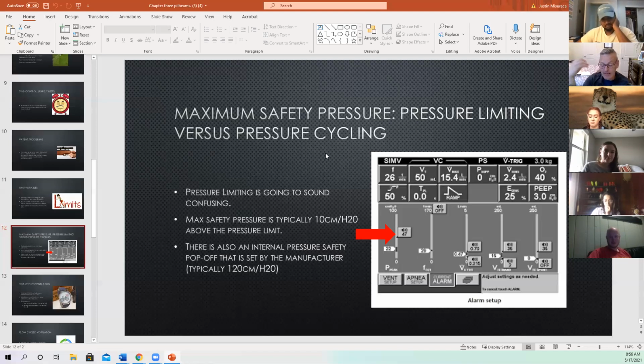Maximum safety pressure. We limited the pressures, so remember we were pressure limited before we set that pressure. It's not going to go any higher. Pressure limiting is going to sound a little confusing because there are two different types. Don't make it more confusing than it is. We limit that pressure by saying, I don't want it to go over 30 or 40 or whatever, so it doesn't go over that when the breath is being delivered. If that failed, there has to be a backup system. The FDA requires backup systems in the ventilators, safety systems, right? The safety systems typically built in and required by the FDA are 120 centimeters of water pressure, which is the max that the ventilator will hold within the circuit before it dumps. So yes, there's the one for that specific patient that we can adjust. This is a factory, manufacturer one that sets the dump off at 120.